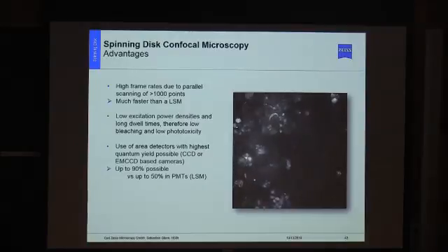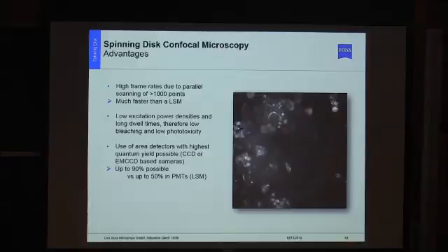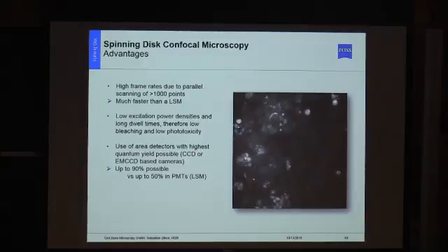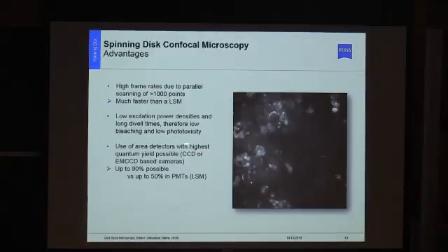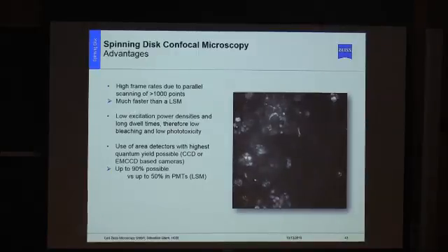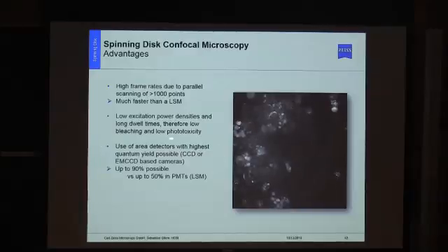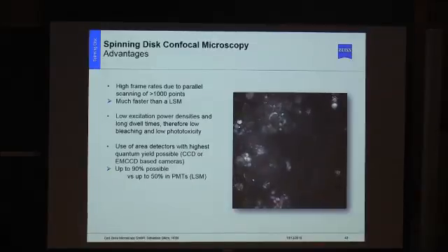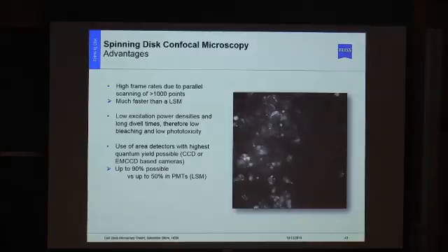The spinning disk system is much faster than a confocal point scanning microscope. If speed is your main objective and you still want confocal-quality imaging, you should use a spinning disk system. Another advantage is that you can use lower excitation powers compared to a confocal scanning system, giving less bleaching and lower phototoxicity. Additionally, you can use camera detectors with quantum efficiency up to 90%, whereas conventional laser scanning microscopes with PMTs hardly reach 50%. So if you want to image dim samples and image them very fast, the spinning disk is the way to go.